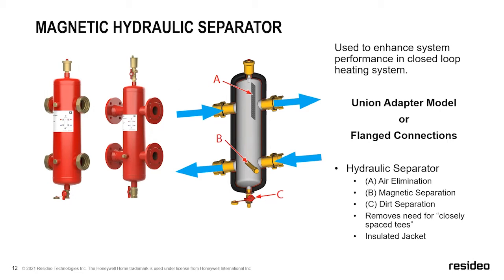So if you had a fixed speed PSC type motor, you might get 15, 25 years out of it. But if you had it in the same system with variable speed without any kind of way of collecting that magnetic material, you may see that thing failing in 3 to 5 years. So magnets are starting to become more and more common and requested in hydronic systems. So we are including a magnetic separation device with every single one of our hydroseps. It's a great place to put it. It's centralized between the boiler and the system, so your water is going to pass through at that point. So regardless of what side of the system that lies on, it will get trapped here in the hydrosep.